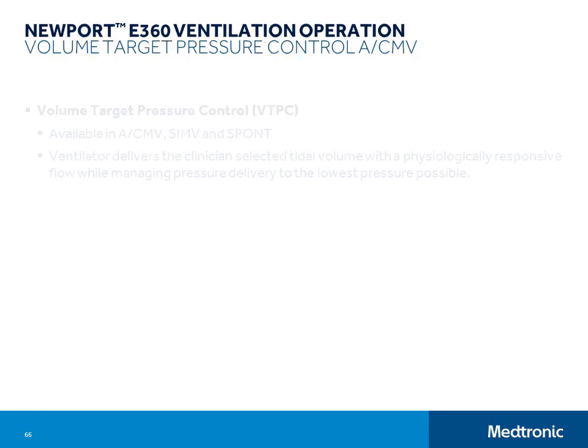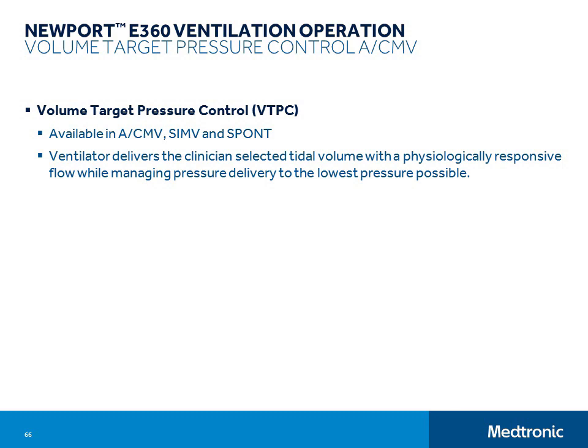The other advanced breath type is volume target pressure control, which we abbreviate as VTPC. This is available in ACMV and SIMV modes, and there is a spontaneous version that's available in SIMV and SPONT modes. Volume target pressure control allows the ventilator to deliver the therapeutically selected tidal volume with a physiologically responsive flow while managing pressure delivery to the lowest pressure possible. This breath type is very easy to set up.